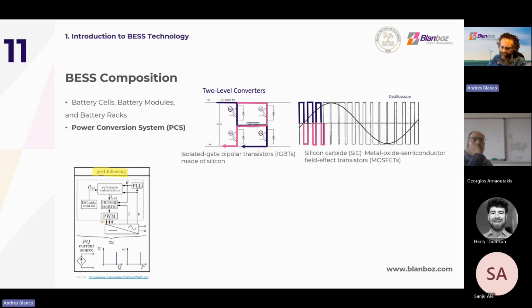In other words, grid forming doesn't need any reference. It can control and synchronize to whatever is needed through droop control, virtual machine and inertia, and virtual oscillators, which are the key main points of grid forming capabilities in a PCS.